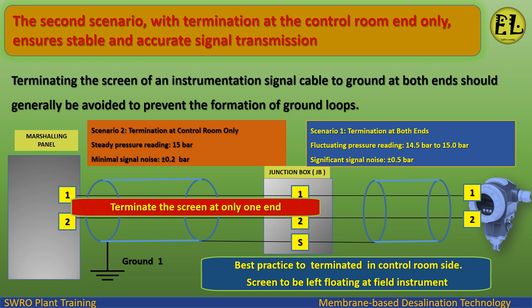Scenario 2, termination at control room only, produces a steady pressure reading of 15 bar with minimal signal noise of plus or minus 0.2 bar. Best practice is to terminate the screen at the control room side only, with the screen left floating at the field instrument end. Thank you for watching this video.